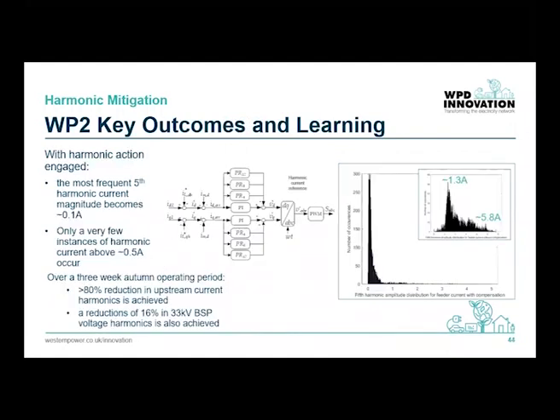But with the harmonic controller enabled, we see a very different picture from the 3-week period. The most frequent magnitude has reduced from approximately 1.3 amps to around 0.1 amp. Without mitigation, the peak 5th harmonic current was around 5.8 amps, and with mitigation, there are very few instances of current above 0.5 amps. A small number of higher current magnitudes that do exist occur during periods when the inverter is using all its capacity to convert renewable power, so can't act on harmonics.